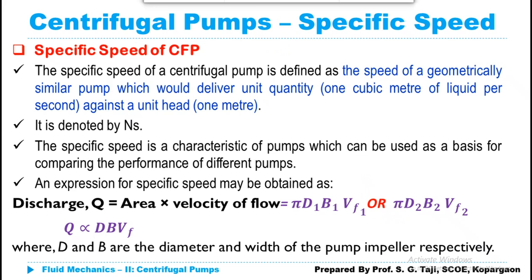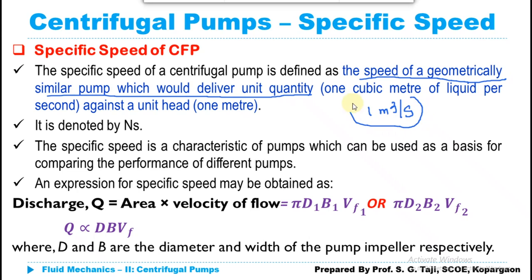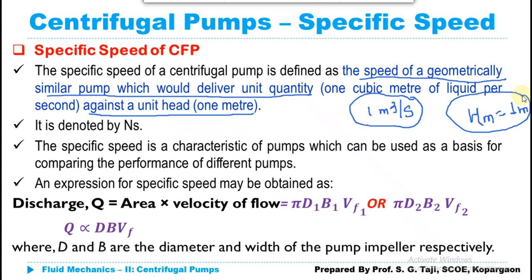Similar to our previous definition, specific speed is the speed of a geometrically similar centrifugal pump which would deliver unit quantity of liquid — that is, one cubic meter per second — when it is working against unit head, that is, when the manometric head is one meter. So when my manometric head is one meter and my discharge is one cubic meter per second, whatever the speed of the pump is, that is known as the specific speed of that centrifugal pump.